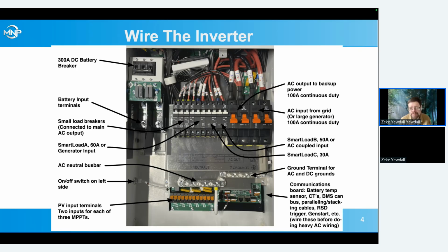Now, one thing to note is that all the communications are behind a lot of our big AC wires. So we really want to think about wiring our communications first before we run all our big wires in. That's kind of the backwards of the way we like doing it. Usually it seems like we always want to put the big wires in first and then go to our small cables. But if we put all of our communications in there first, it'll be a lot easier. Same with our PV wires. They sometimes end up being behind some of the other cables if we can put those in there first.